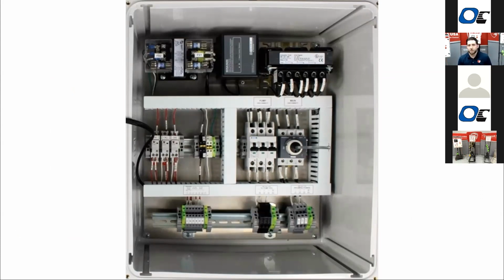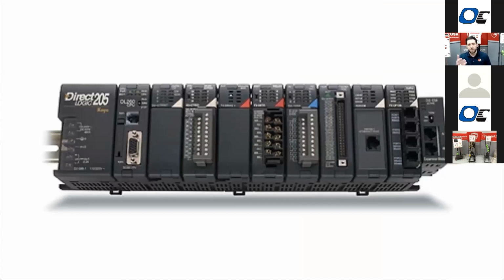So these are good for single pump applications or alarm panels, things like that, where you just need a little bit of feedback or maybe a single pump control. Beyond the simple applications, it starts to get a little prohibitive in the design with the amount of relays it takes to make the design work. So that's when we would move up to this PLC and touchscreen driven design.